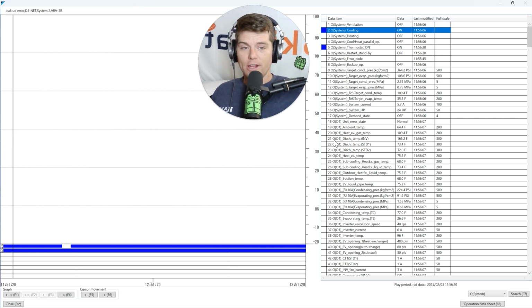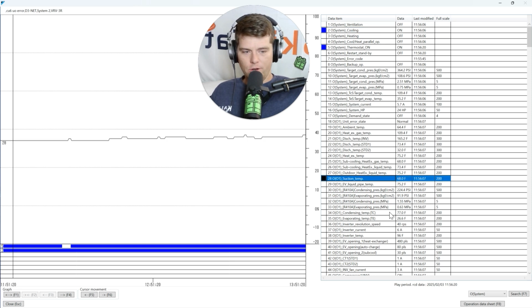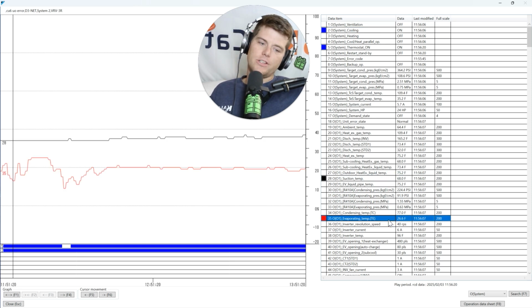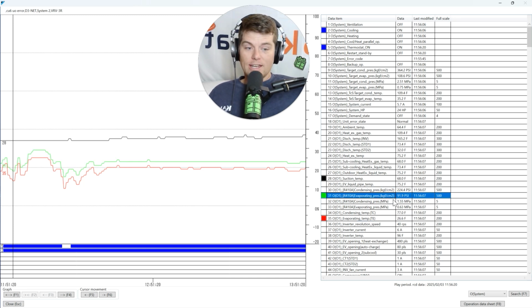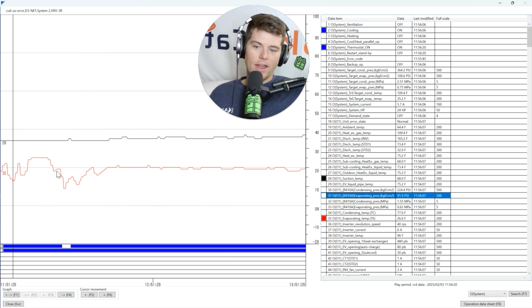Suction superheat is the measurement of the quality of vapor returning to the compressor. It tells me the quality in regards to, is it a liquid? Is it a vapor? Is there enough of it getting back to the compressor? All those things are determined with suction superheat. So what we do now is take our suction temperature of our unit and our TE, which is evaporator temperature spelled backwards. With evaporator temperature, this is 91.9 PSIG in R410A converted to saturation temperature. That's how we get TE. If you didn't know that, now you know.